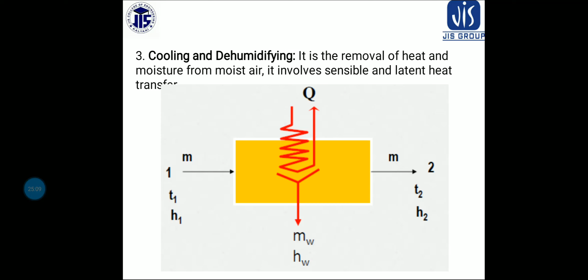You can see in the psychrometric chart the dew point temperature is shown, and dehumidification is basically cooling. In the cooling coil, the temperature of air reduces and the saturation point, that is your dew point, is reached. Further cooling results in a reduction of the absolute humidity.